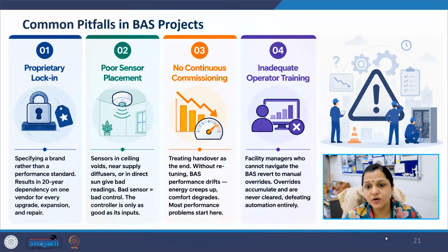Now we are discussing the common pitfalls. The first mistake is proprietary vendor lock-in. When projects depend entirely on one vendor, future upgrades and maintenance become expensive and restricted. The second mistake is poor sensor placement. A bad sensor reading creates a bad control decision. The third mistake is neglecting continuous commissioning. Without periodic retuning, energy performance gradually degrades. The fourth mistake is inadequate operator training.